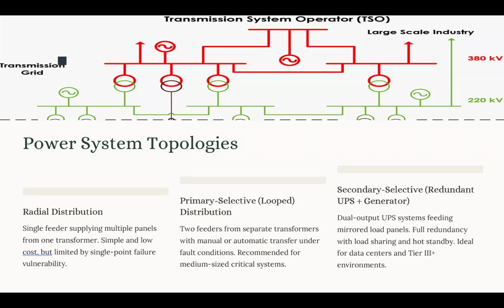As we said, there are some advantages. One would be the cost effectiveness of this topology and ease of maintenance. It has a simpler design and needs fewer components, but for the critical sensitive equipment it is not recommended because there is no redundancy, and a voltage sag or transient from one load propagates to all downstream equipment.